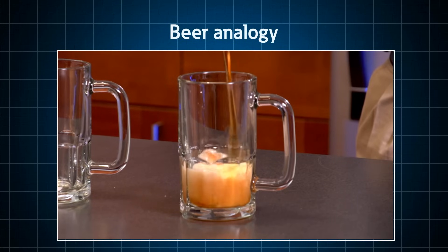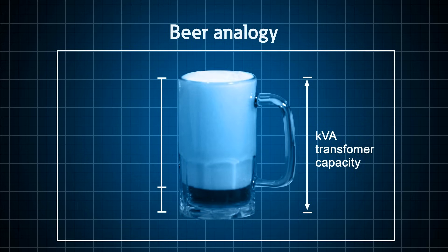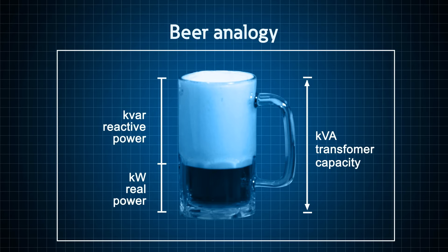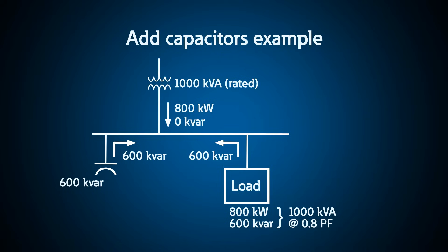Probably the most common analogy to explain reactive power is the beer analogy. The mug size or capacity is compared to the KVA rating of a transformer, which is the transformer's capacity. Utilities bill us on kilowatts or kilowatt hours, which is real power, or in the analogy is compared to the beer. The foam takes up space and essentially wastes capacity of the mug or the transformer. The foam is compared to the reactive power or KVARs. So if you remove the foam, you can fit more beer in the glass or real power. Adding capacitors compensates for the motor loads on the system and allows you to add more real watts or loads to your transformer.